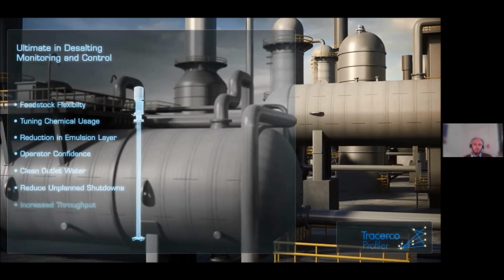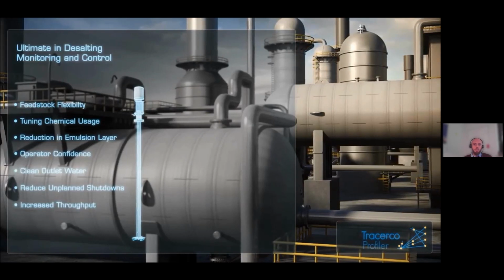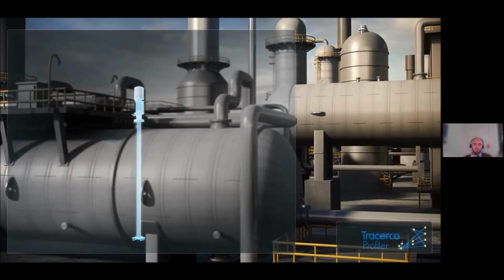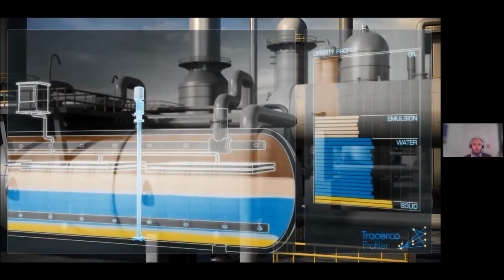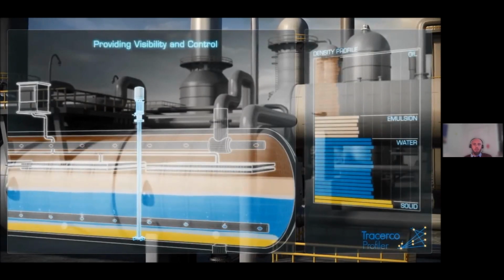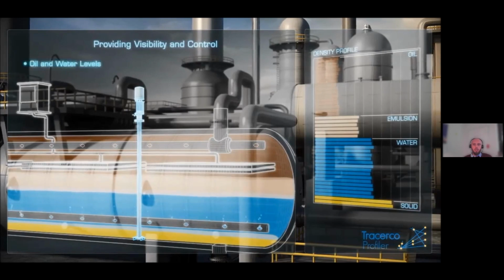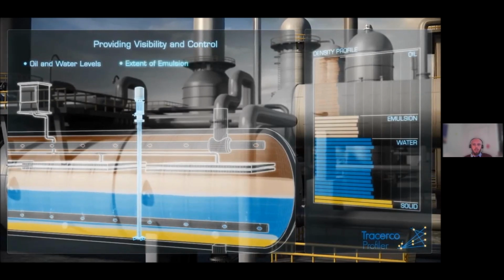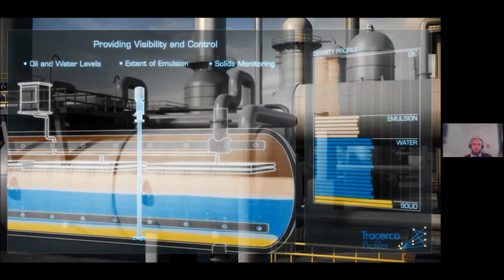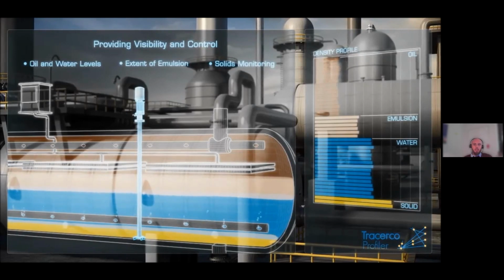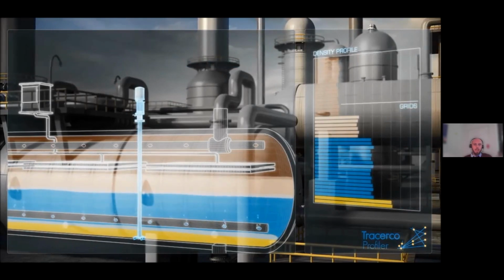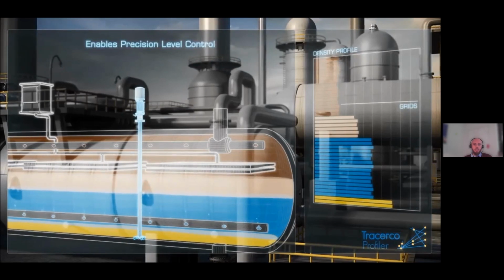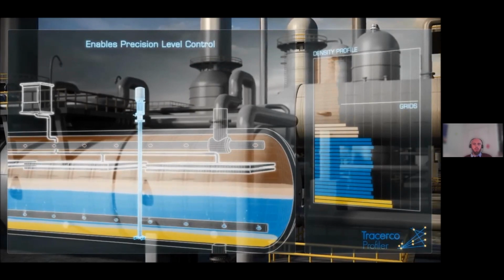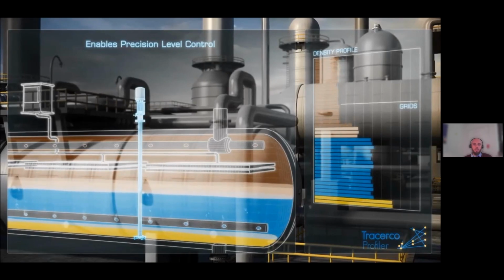It's also going to show a graphic on the right-hand side, which is similar to what the HMI will show in real time for the output. So using these outputs, you'll be able to see the oil, water, and emulsion or foam, to the extent of any buildup in the vessel. And the profiler can have level, alarm, and trip functions taken from the same profiler and the same output, which should prevent any dangerous configurations from happening.